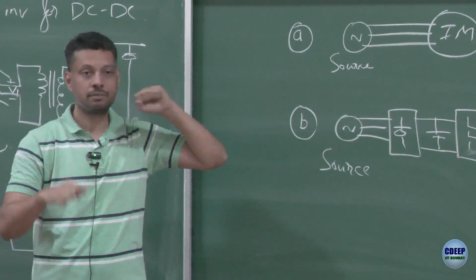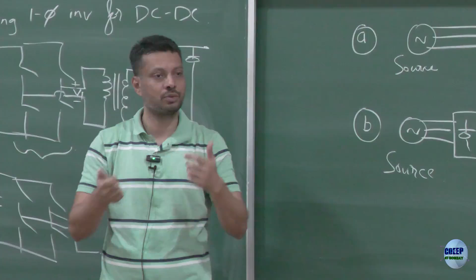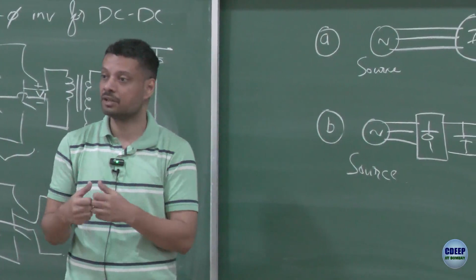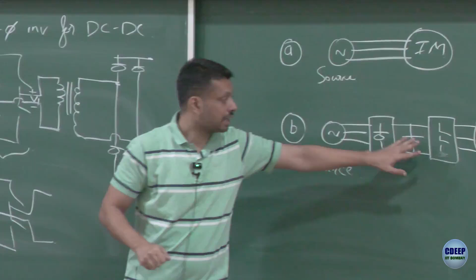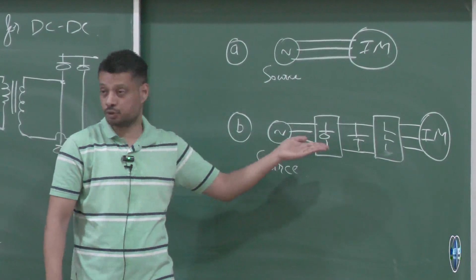So wherever you need smooth speed control or smooth torque control, you have to do this. Because in the other case, as soon as it connects, it just gives a certain voltage applied to an induction motor, and the motor responds to that sudden voltage. But here we can start slowly, do V by F control, slowly build up small voltage and increase it to 230, because you can control the voltage going into the induction motor. So in most cases here you can do speed control, but there is no speed control there.